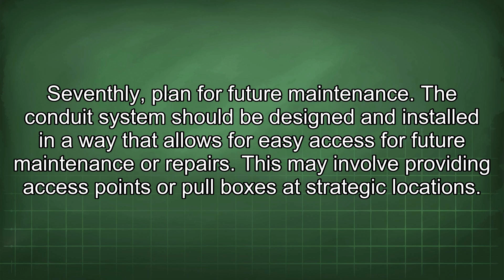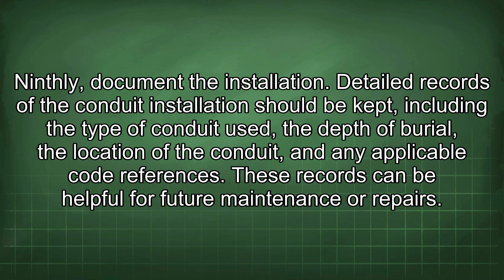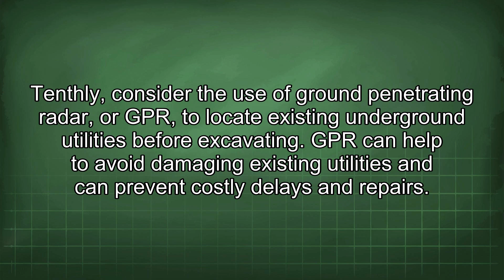Ninthly, document the installation. Detailed records of the conduit installation should be kept, including the type of conduit used, the depth of burial, the location of the conduit, and any applicable code references. These records can be helpful for future maintenance or repairs. Tenthly, consider the use of ground-penetrating radar, or GPR, to locate existing underground utilities before excavating. GPR can help to avoid damaging existing utilities and can prevent costly delays and repairs.